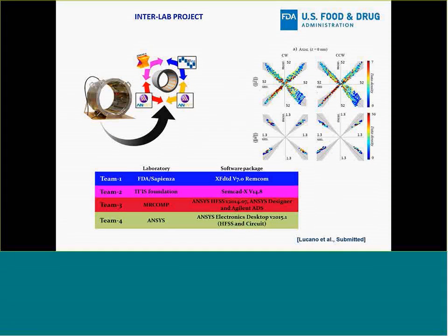Another area that we're working in collaboration with other groups, ANSYS, IT'IS foundation, and MRCOMP, is an interlab analysis of a coil. So we have taken a physical coil available in our labs. We have distributed some information, limited information, to 4 different groups with different experience in terms of evaluation of electromagnetic fields, different experience in terms of MR safety, which have used each different software platforms and approaches which were really left to them.